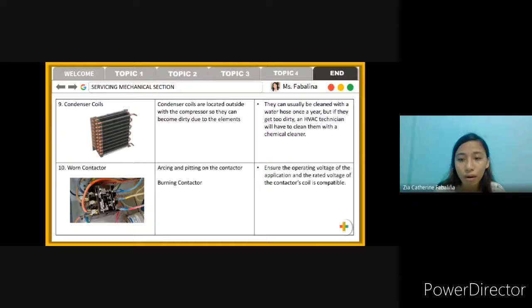Last is the worn contactor. Arcing and pitting on the contactor are some of the troubles that our contactor experiences. The best solution is to ensure the operating voltage of the appliance and the rated voltage of the contactor coil are compatible. So that is the part of our aircon that is very prone to trouble.